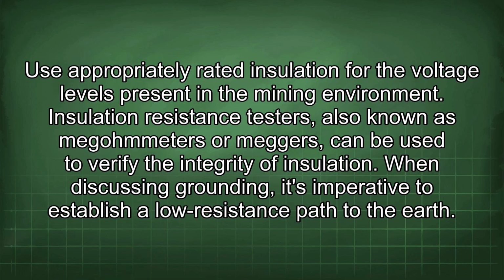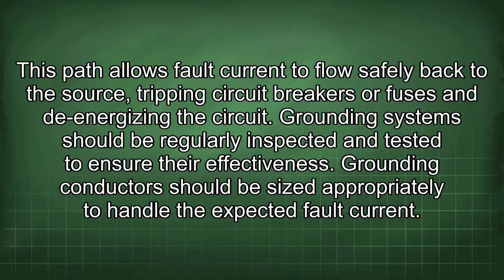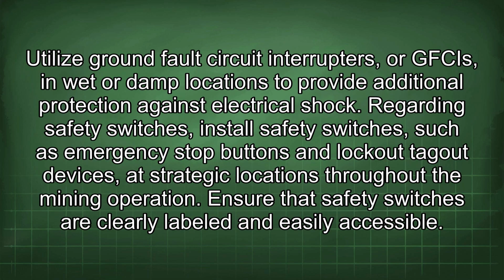When discussing grounding, it's imperative to establish a low resistance path to the earth. This path allows fault current to flow safely back to the source, tripping circuit breakers or fuses and de-energizing the circuit. Grounding systems should be regularly inspected and tested to ensure their effectiveness. Grounding conductors should be sized appropriately to handle the expected fault current. Utilize ground fault circuit interrupters, or GFCIs, in wet or damp locations to provide additional protection against electrical shock.